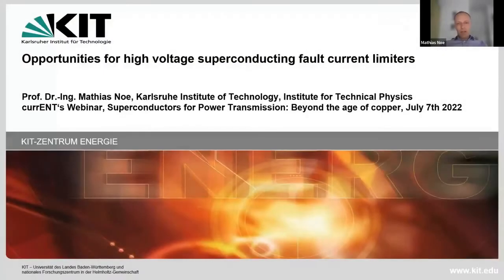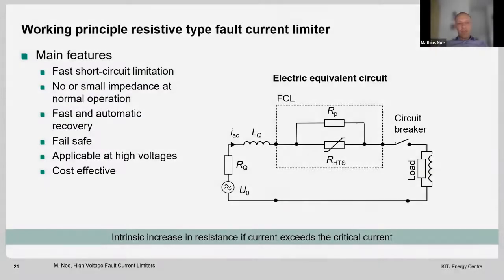Before we continue with the cables, I want to shortly introduce the opportunities for superconducting fault current limiters. The main features are fast short circuit limitation within the first current rise, no impedance at normal operation, and fast automatic recovery if the circuit breaker opens for some time. It's fail-safe, meaning even if the superconductor fails in the middle, you limit the current anyway and protect your equipment. And it's applicable at high voltages, and in some cases already cost effective.